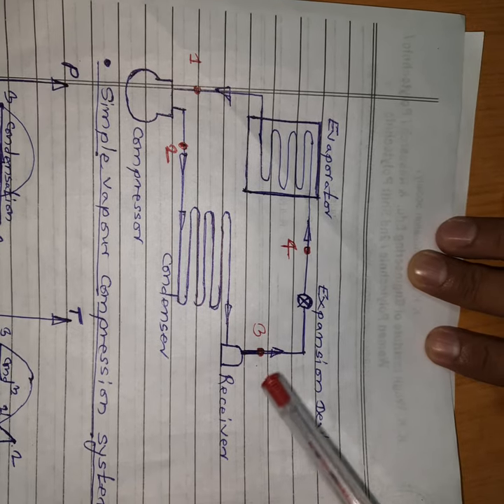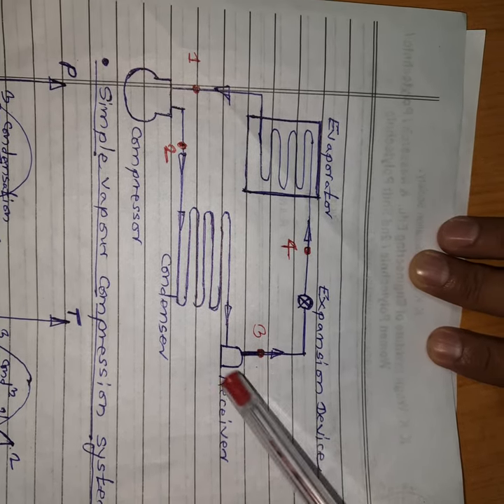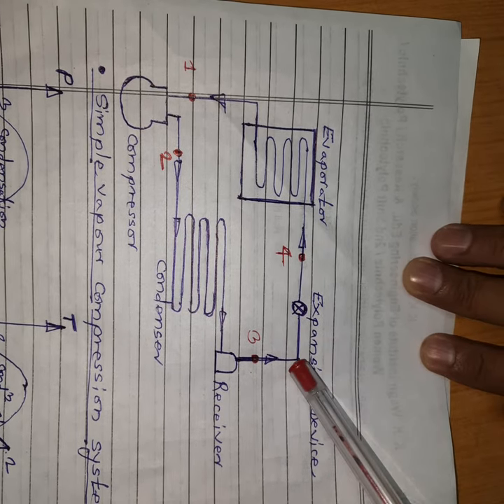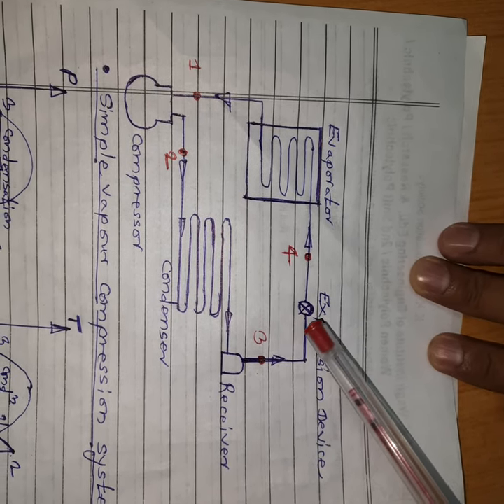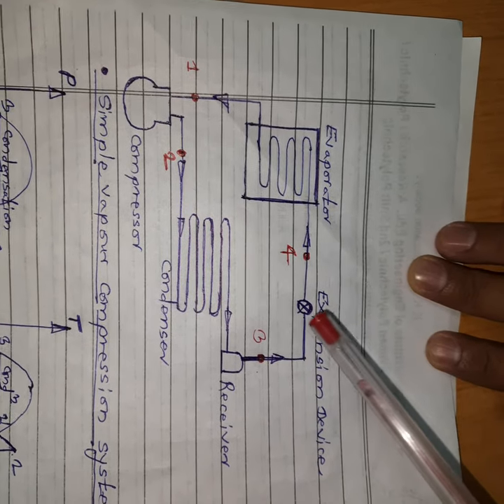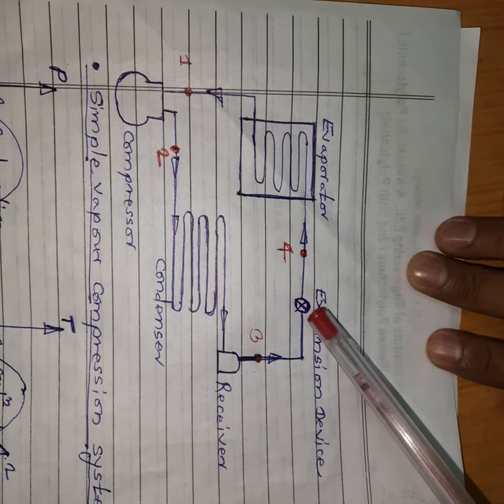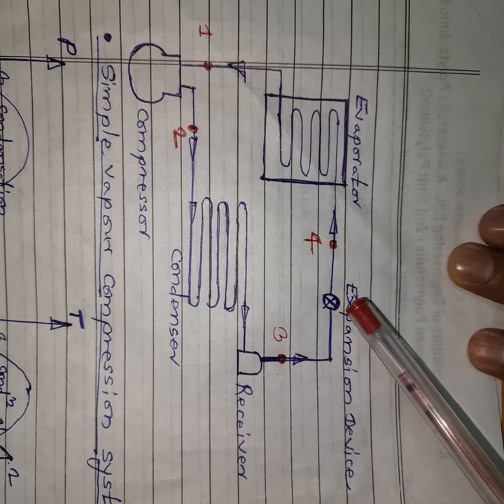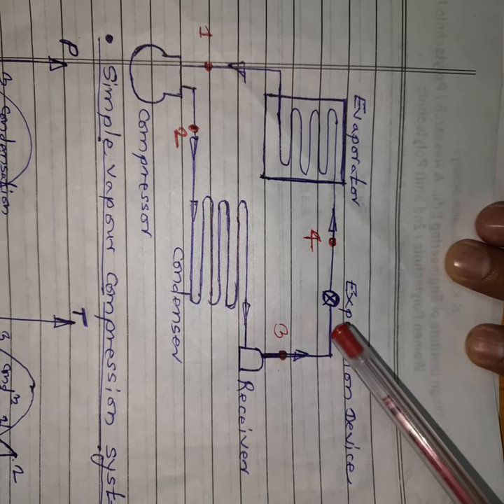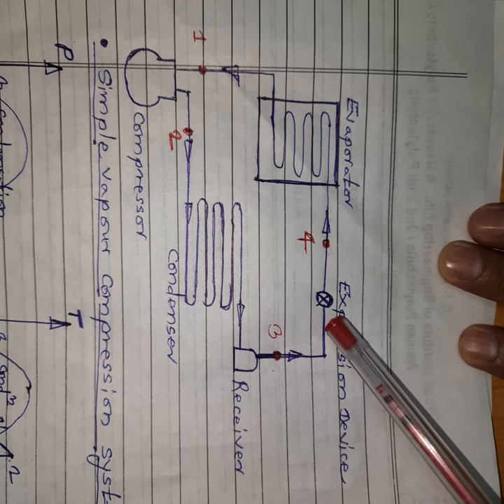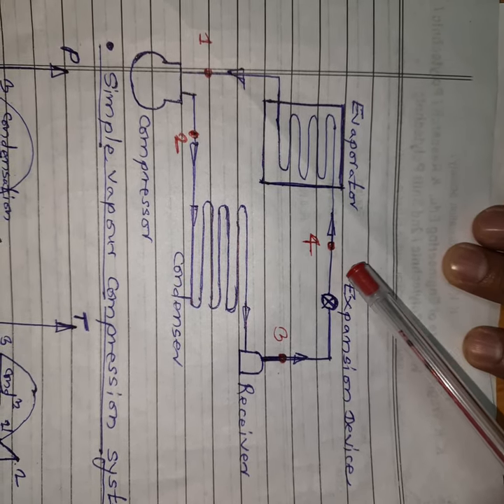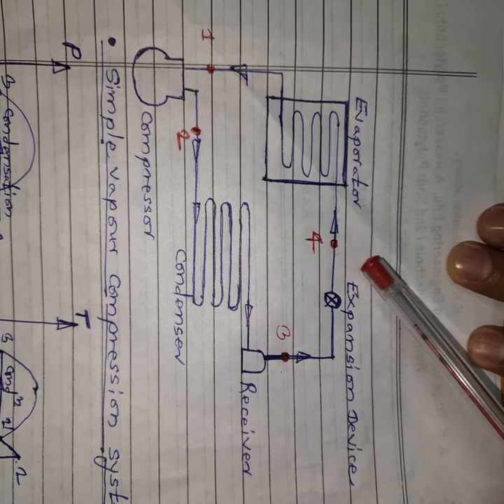The receiver is a device used for storage of the refrigerant before supplying it to the expansion device. In the expansion device — a capillary tube — the high pressure raised by the compressor is decreased. High pressure, normal temperature liquid refrigerant enters, and when leaving there is a decrease in pressure and accordingly a decrease in temperature.